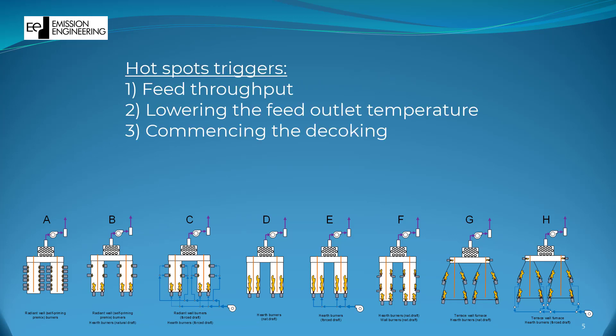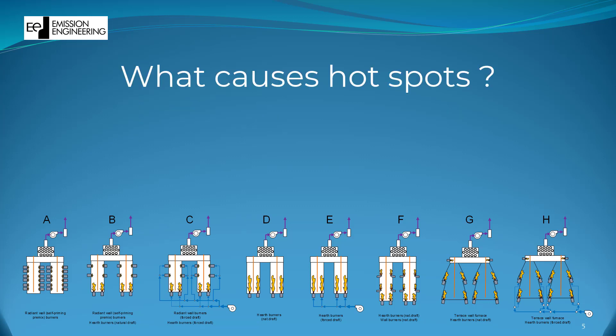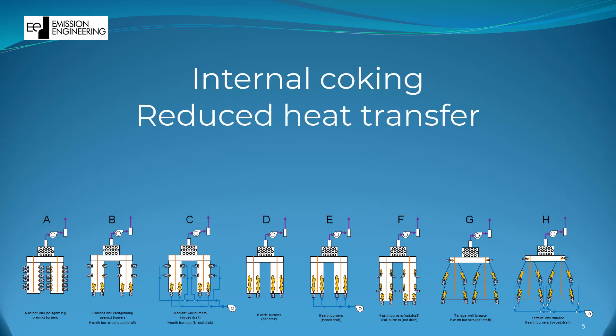High coil temperatures, often referred to as hotspots, are normally the parameters that trigger feed cuts, lowering of the feed outlet temperatures, or the necessity for decoking. But what actually causes high coil temperatures? Normally it is caused by internal coking of the feed, leading to lower heat transfer rates in the radiant coils.